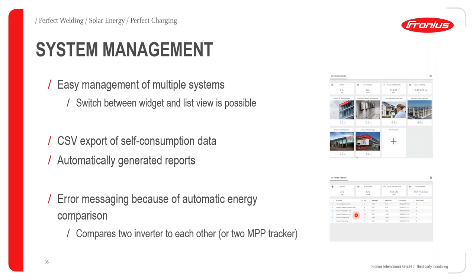SolarWeb also allows you to export self-consumption data as CSV files, including automatically generated reports, and gives you the opportunity to diagnose errors across one or many systems. You can compare between two inverters in one system, or compare the performance of two MPPTs within the same inverter, to know if something needs to be checked.